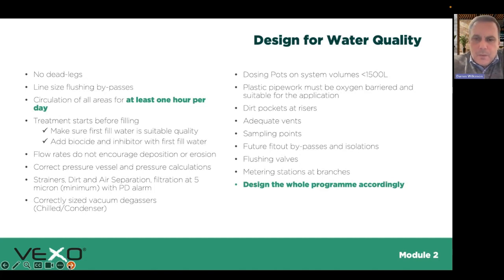People have caught onto it, but a lot of plastic pipework was being installed that didn't have an oxygen barrier. So it wouldn't let water out of the pipework, but it would almost breathe. It would let oxygen in. And the Ministry of Defence had a project years ago where they were changing radiators after 3 months, costing millions, because they created this huge chemical reactor. We do recommend dirt pockets at the bottom of risers, so anything heavy, particularly on the pre-com cleaning, you can grab it without it causing damage around the system.